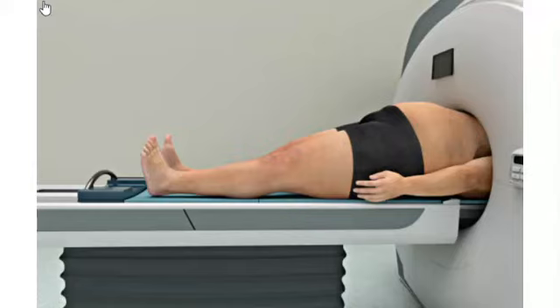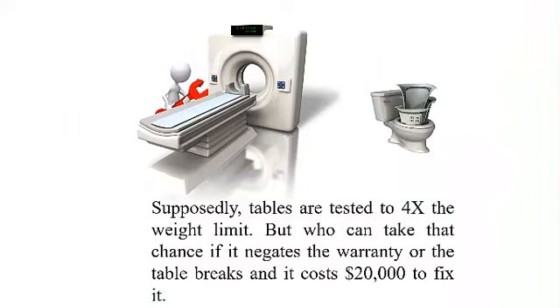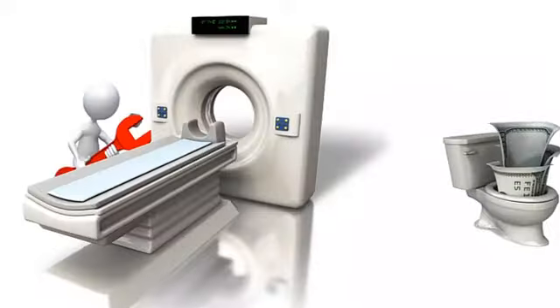The table might support the weight if it is moved to the level of the gantry aperture before the patient is loaded, but once they're in, how do you move them up and down? Theoretically, tables are tested to 4 times the weight limit, but who can take that chance if it negates the warranty or the table breaks and it costs $20,000 to fix it?